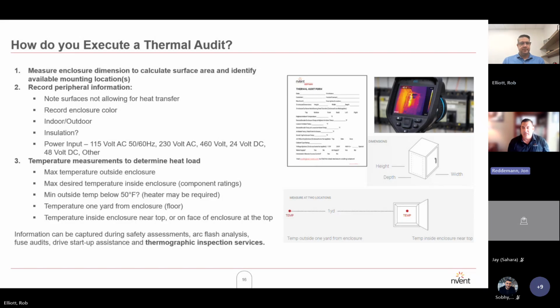And we want to take the temperature about 3 feet away from that panel. And then we want to take the temperature inside the panel with that process running. And what we're looking for again is that delta. We need to know what the temperature difference is with the system running versus 3 feet away.